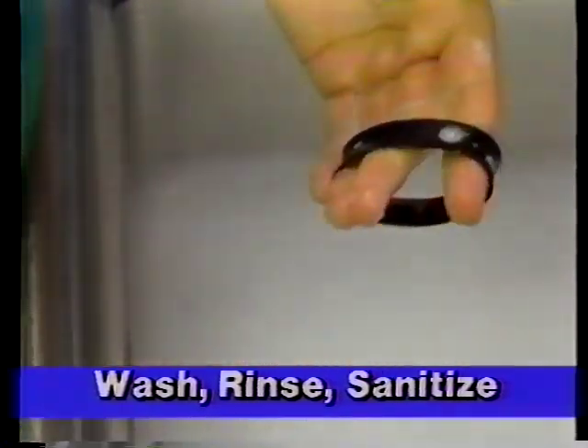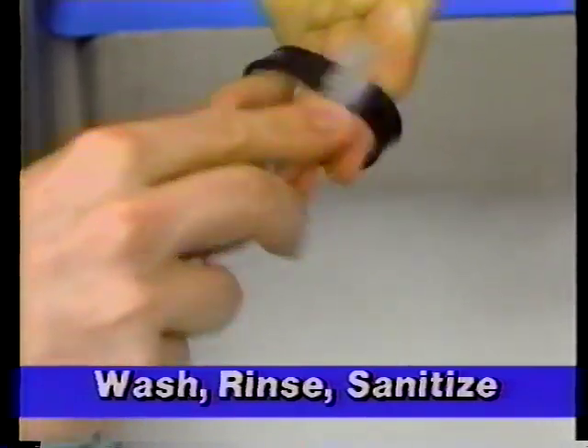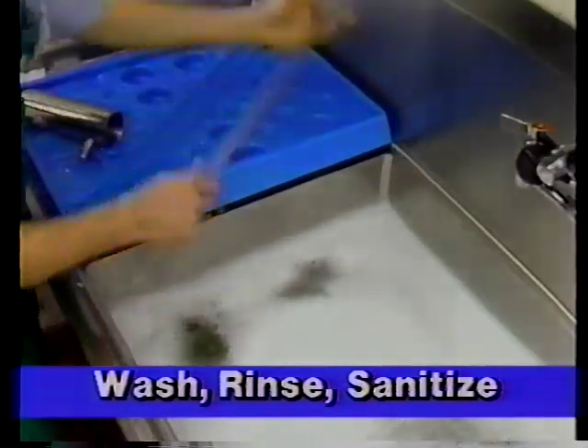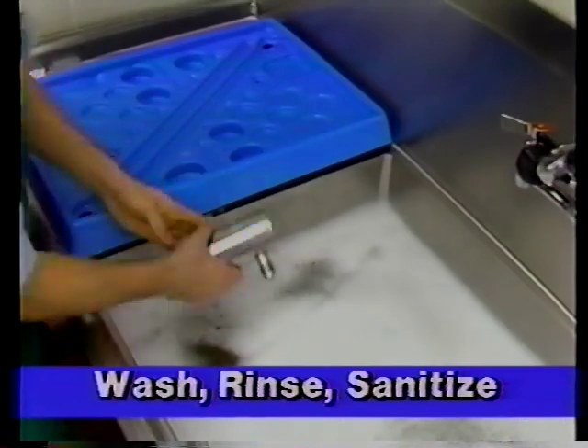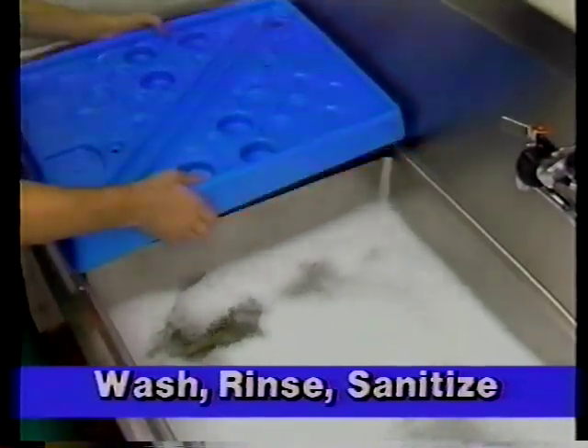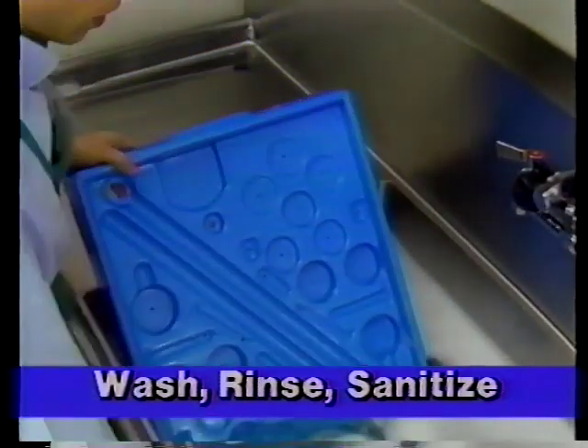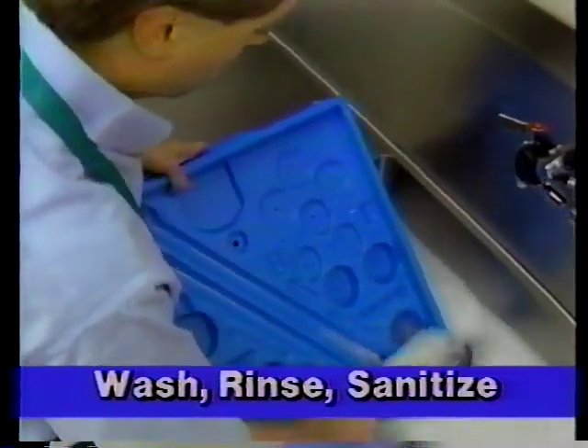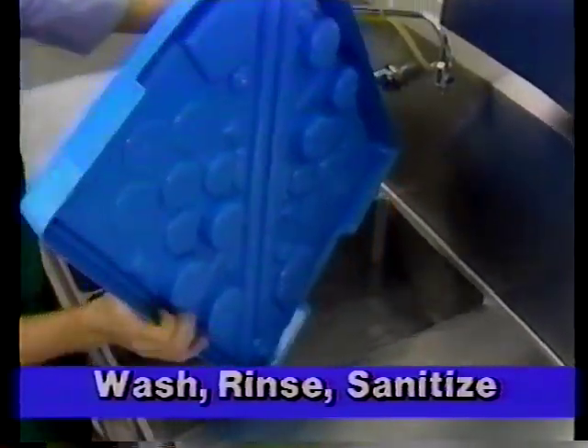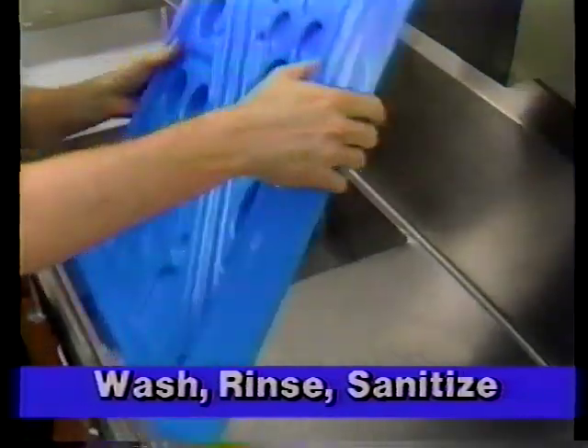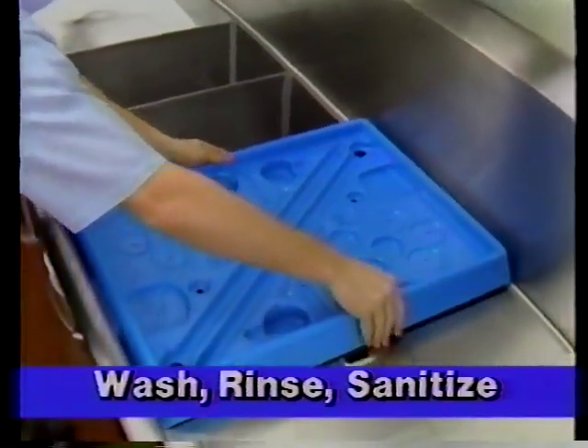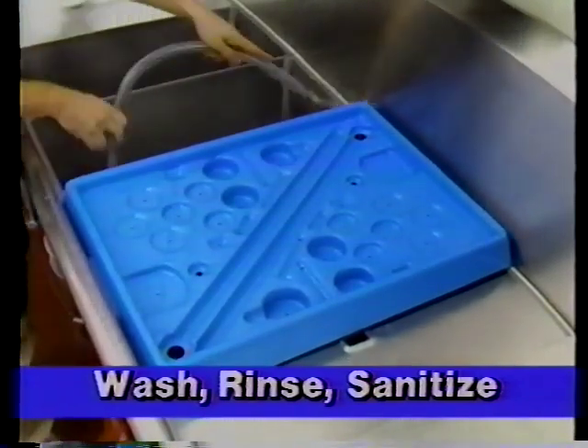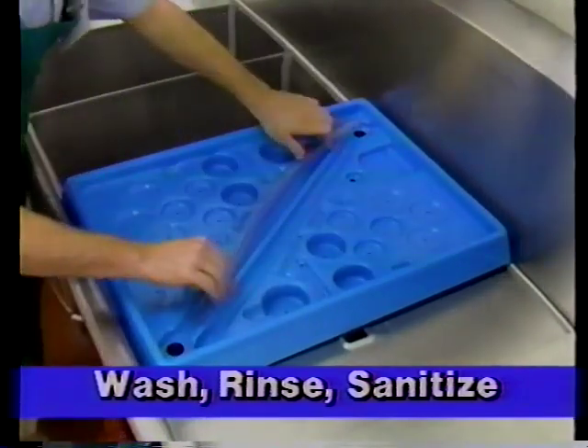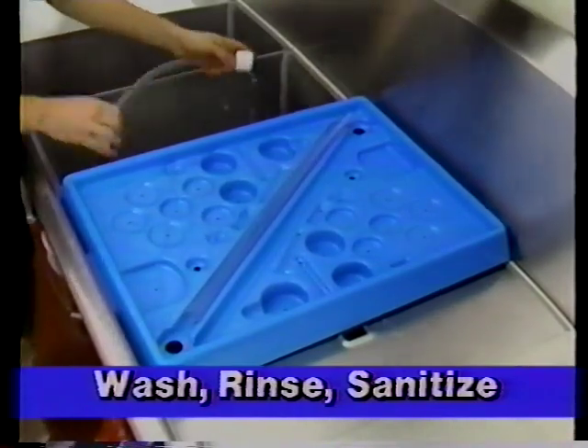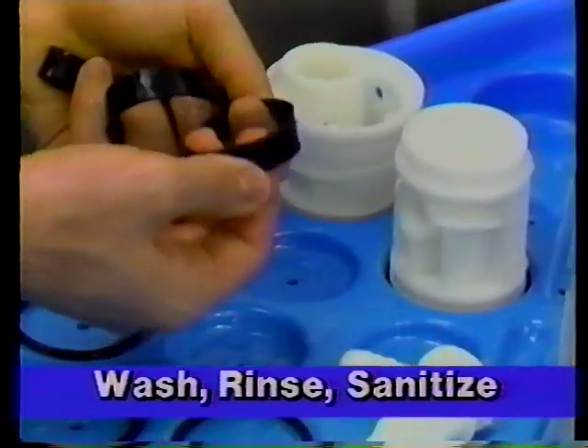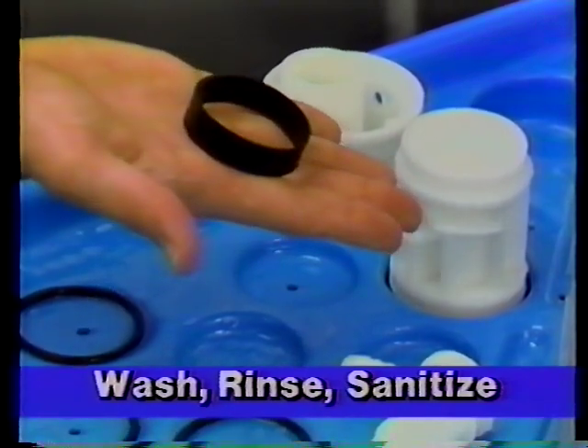Once you have all the plastic and rubber parts in the sanitizing solution, you should place the remaining stainless steel parts in the wash compartment. And then take the parts tray through the same cleaning process. So you'll have it ready to put all the sanitized parts on. Remove all the plastic and rubber parts from the sanitizing solution and place on the parts tray to air dry. Make sure you keep the check bands turned right side out. That means flat side out.